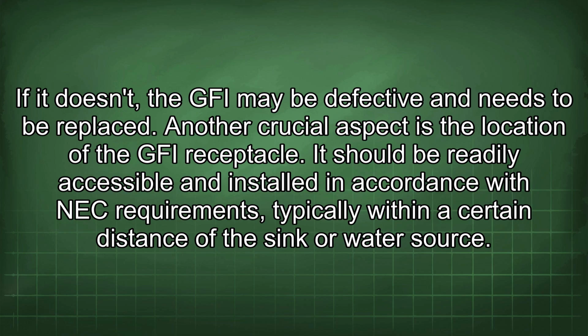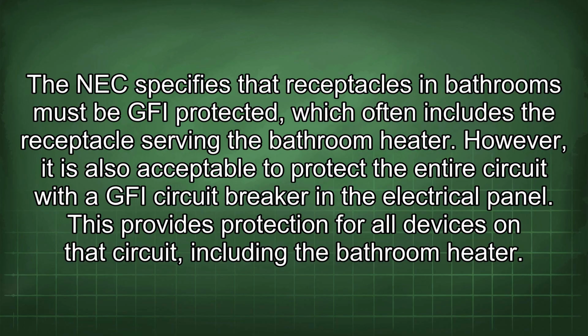Another crucial aspect is the location of the GFI receptacle. It should be readily accessible and installed in accordance with NEC requirements, typically within a certain distance of the sink or water source. The NEC specifies that receptacles in bathrooms must be GFI protected, which often includes the receptacle serving the bathroom heater. However, it is also acceptable to protect the entire circuit with a GFI circuit breaker in the electrical panel. This provides protection for all devices on that circuit, including the bathroom heater.